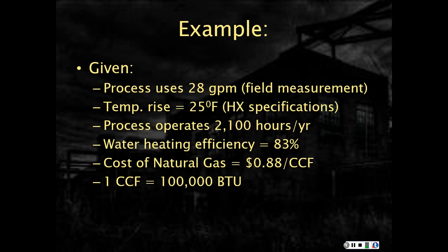Now, the process uses, in this particular example, 28 gallons per minute. This is a field measurement. The temperature rise, which we determined at 25 degrees, came from working with a heat exchanger manufacturer looking at various types of heat exchangers and their specifications. This turned out to be the optimal between first cost, area where we can put it, installation cost, operation, and variations in the operation. So a number of factors went into that. The process itself operates 2,100 hours a year. The heating efficiency on that overall process is 83%. Natural gas is currently being purchased at 88 cents per CCF, and 1 CCF is equal to 100,000 BTUs.